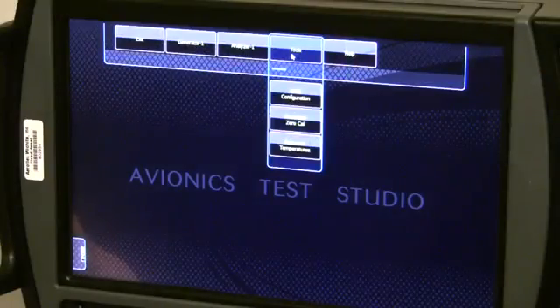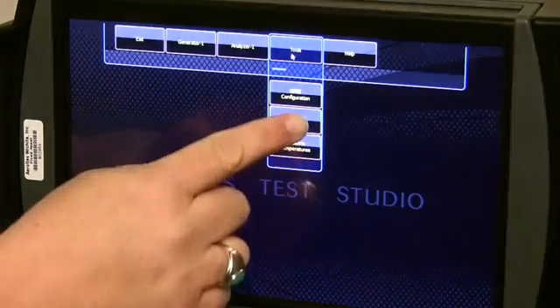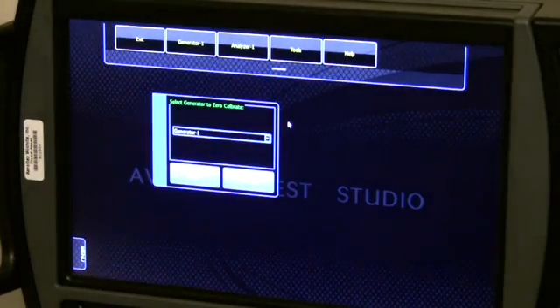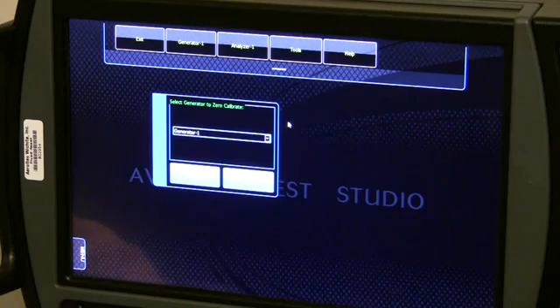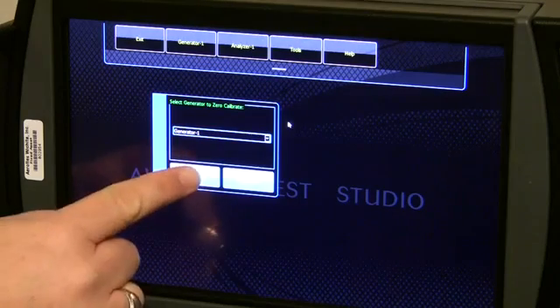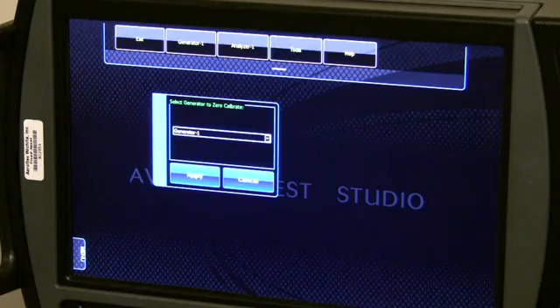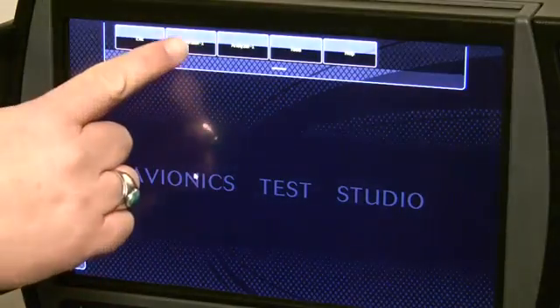The generator should be zero calibrated before each operation. To perform the zero cal, press the Generator 0 Cal button. Now let's look at the generator functions.